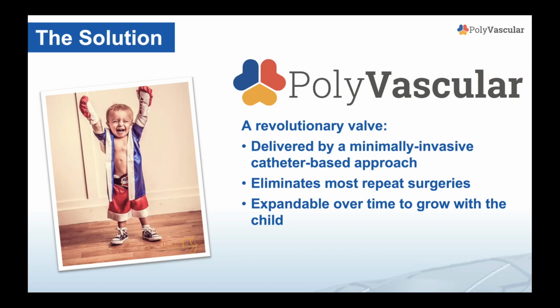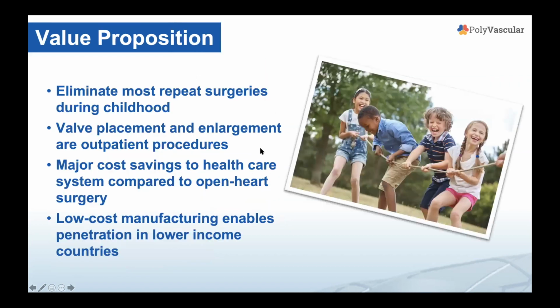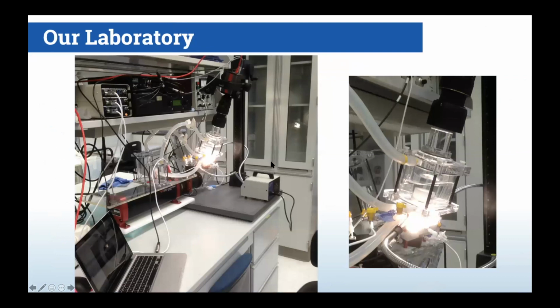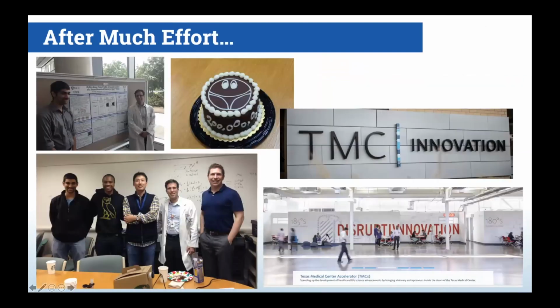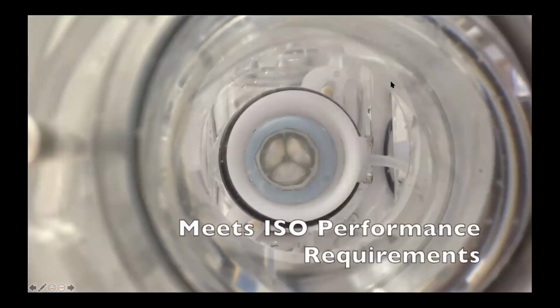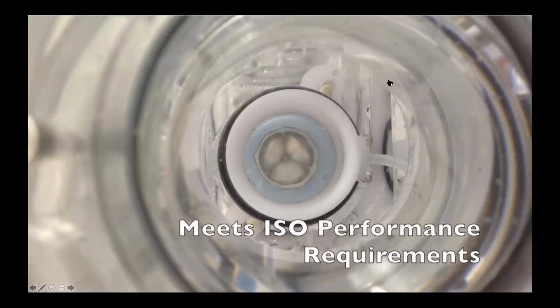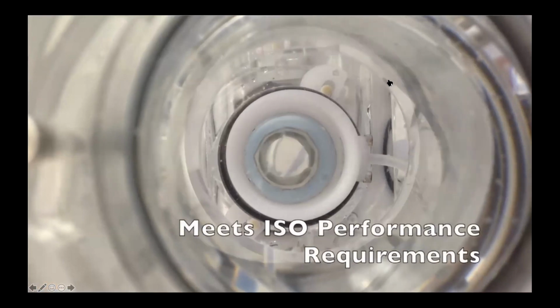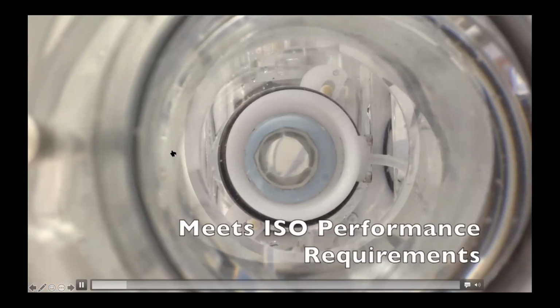And we've even developed the valve to be redilatable over time to grow with the child. And our value proposition is, again, the cost saving to the healthcare system. This is our team here with some of our students working with us. We went through the TMC innovation system. This is our valve operating in a pulse duplicator, showing it opening and closing well. It already meets the International Standards Organization requirements for valve performance.